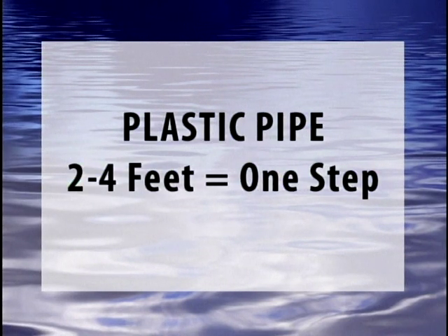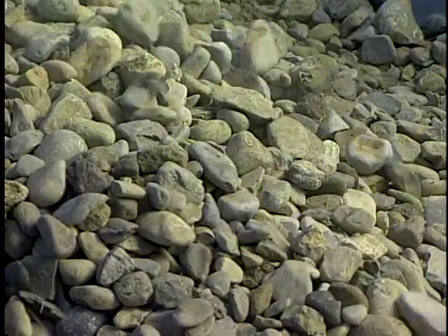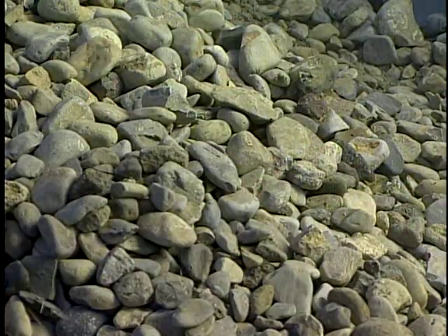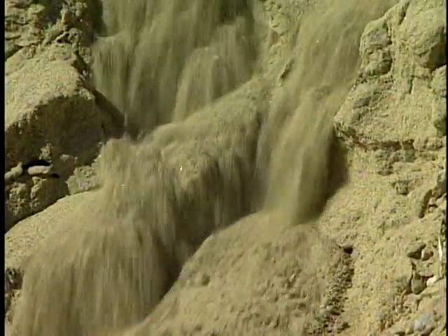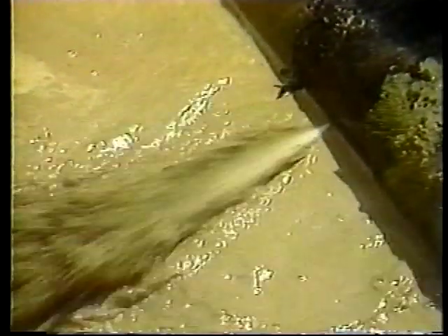When looking for a leak on a PVC or plastic pipe, listen every two to four feet, or one step. Other sounds that can help you pinpoint a leak's location are sounds such as gravel rolling and striking against each other, sand grating against itself or other solid objects, or dirt or rocks falling into the void caused by the erosion from the leak.